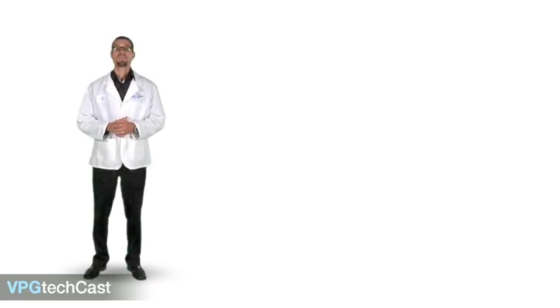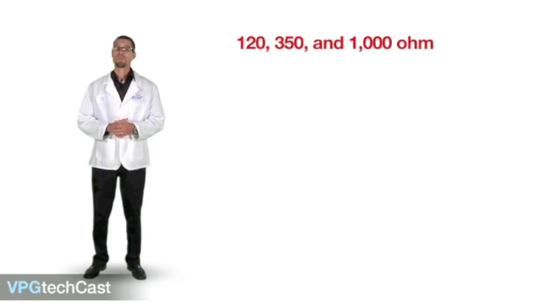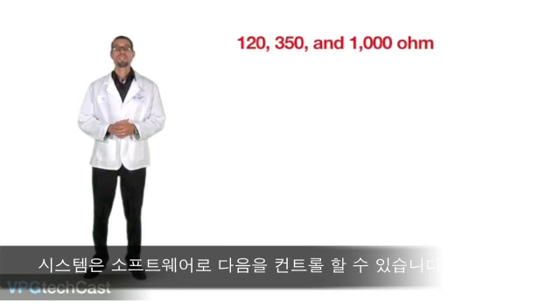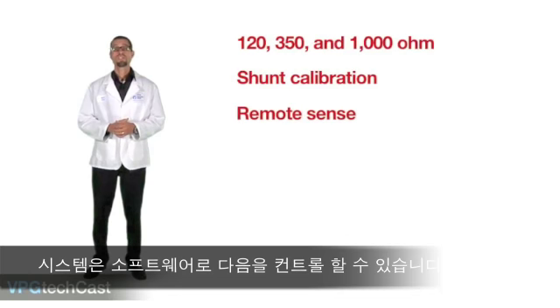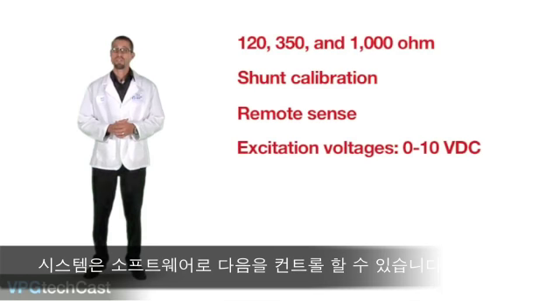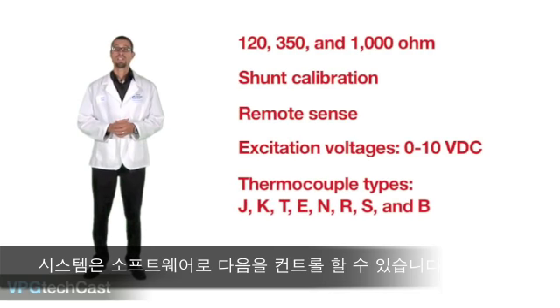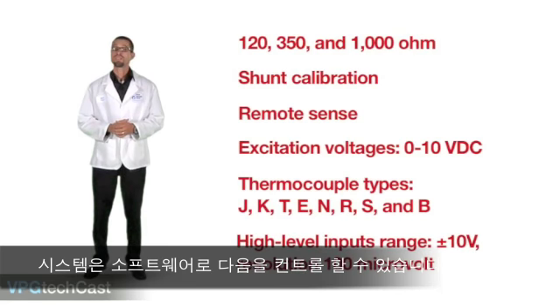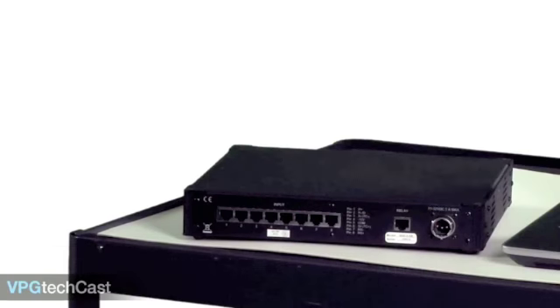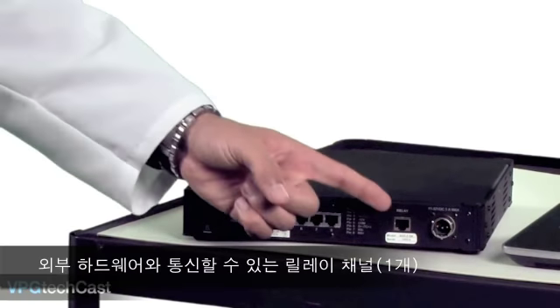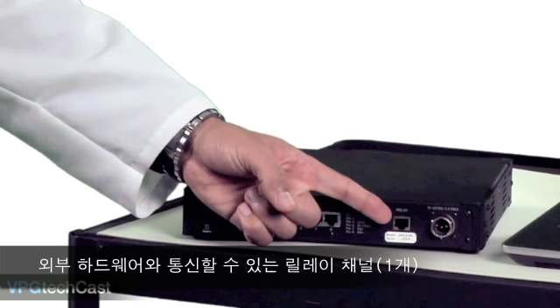The System 8000 offers software selectable internal completion resistance for 120, 350, and 1,000 ohm strain gauges, software controlled shunt calibration, software controlled remote sense, and excitation voltages ranging from 0 to 10 volts DC. The 8000 supports J, K, T, E, N, R, S, and B type thermocouples. High-level inputs can range from plus to minus 10 volts with a resolution of 100 microvolts. The System 8000 has a single normally open or normally closed relay contact for communicating with external hardware.